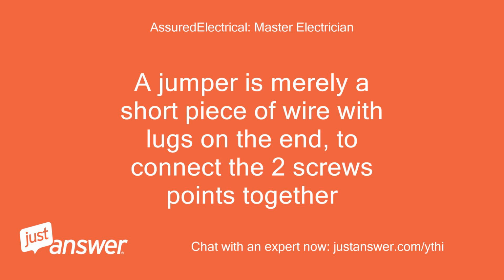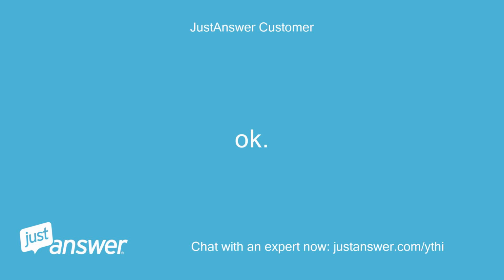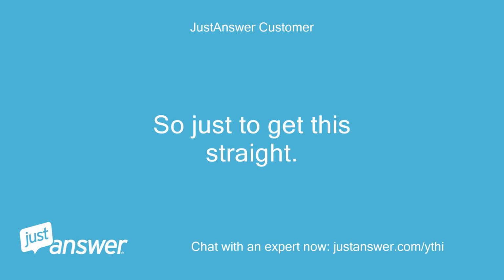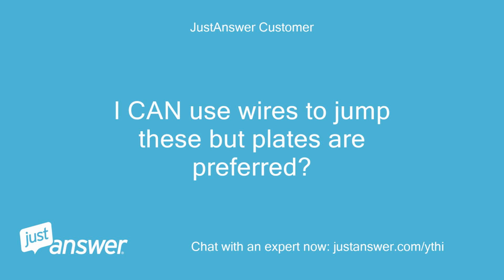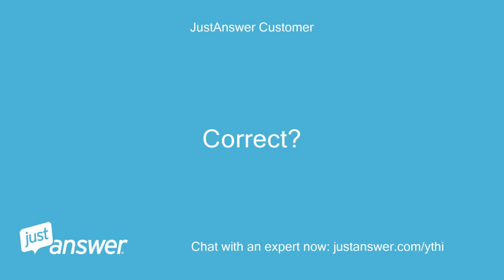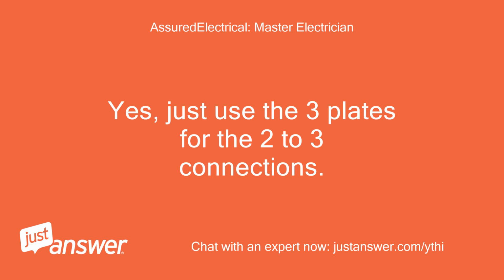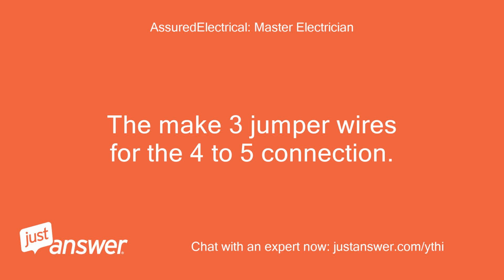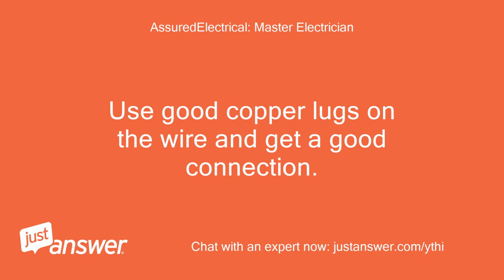A jumper is merely a short piece of wire with lugs on the end, to connect the 2 screw points together. Okay. So just to get this straight, I can use wires to jump these, but plates are preferred. Correct. Yes, just use the 3 plates for the 2 to 3 connections. Then make 3 jumper wires for the 4 to 5 connection. Use good copper lugs on the wire and get a good connection.